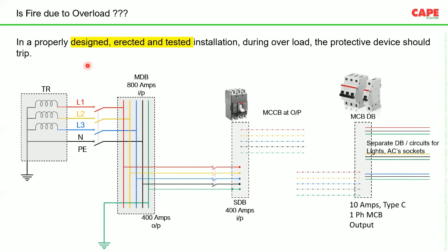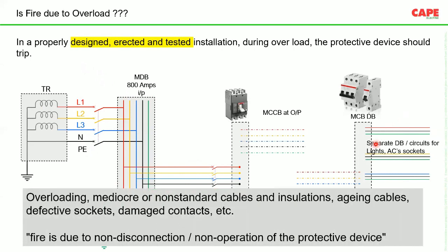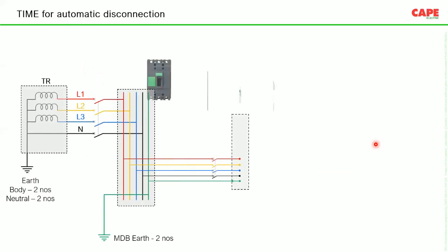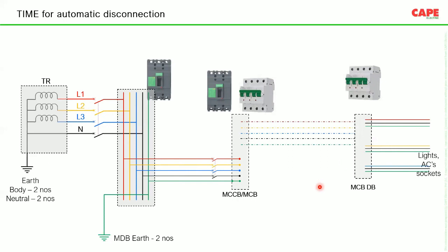Please note that in a properly designed, erected, and tested electrical installation, overload and short circuit shall not create any incident, because these protective devices are supposed to disconnect, provided they are not only selected properly and installed properly, but also tested properly. Most often this testing, especially fault testing, the disconnection of the protective device during an earth fault, is very, very rarely done because we use a kind of TT system.